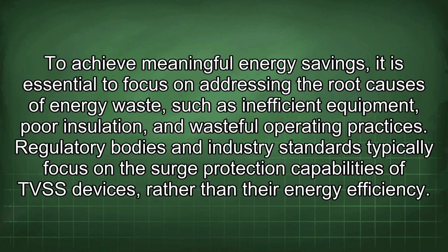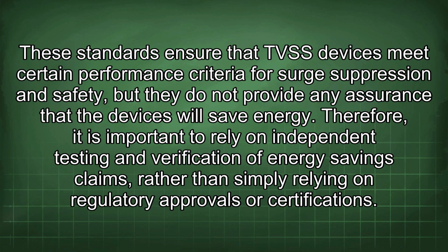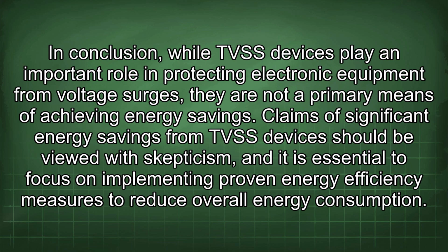Regulatory bodies and industry standards typically focus on the surge protection capabilities of TVSS devices, rather than their energy efficiency. These standards ensure that TVSS devices meet certain performance criteria for surge suppression and safety, but they do not provide any assurance that the devices will save energy. Therefore, it is important to rely on independent testing and verification of energy savings claims rather than simply relying on regulatory approvals or certifications. In conclusion, while TVSS devices play an important role in protecting electronic equipment from voltage surges, they are not a primary means of achieving energy savings. Claims of significant energy savings from TVSS devices should be viewed with skepticism, and it is essential to focus on implementing proven energy efficiency measures to reduce overall energy consumption.